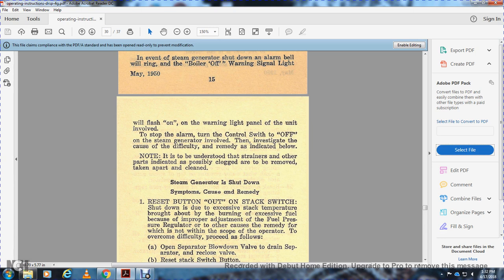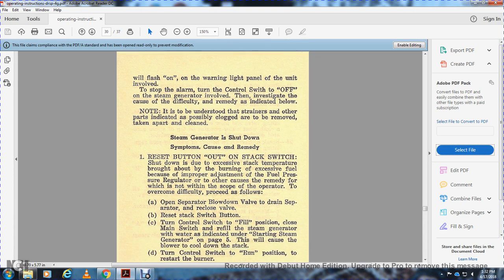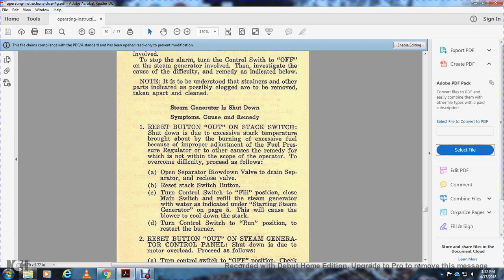the operator to overcome the difficulty: proceed as follows. Open the separator blow down valve to drain the separator, reclose the valve, reset the switch button, turn the control switch to the fill position, close the main switch, refill the steam generator with water, and start the steam generator as indicated on page 5 of this, which will cause the blower to cool down the stack. D, turn the control switch to the running position, restart the burner.